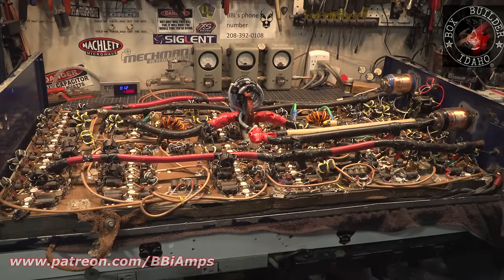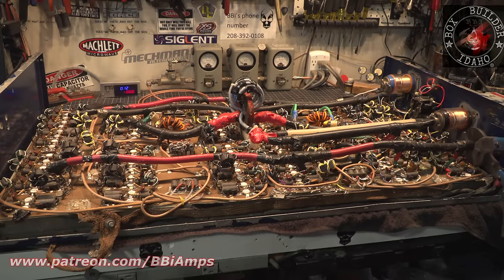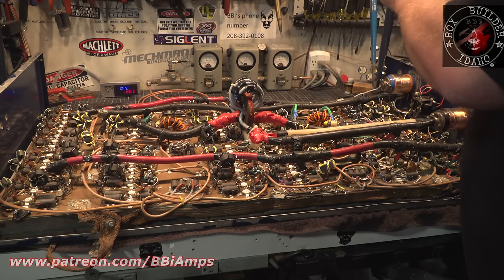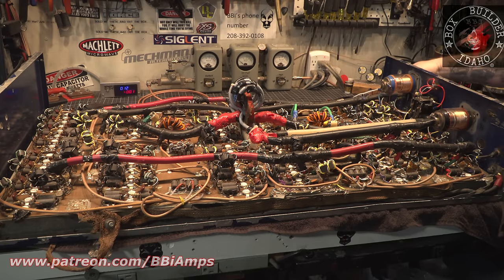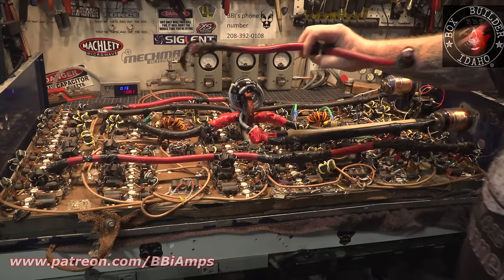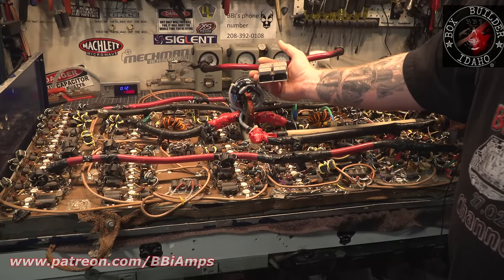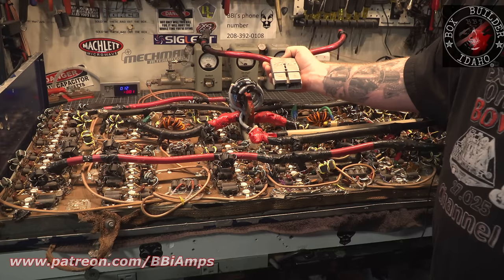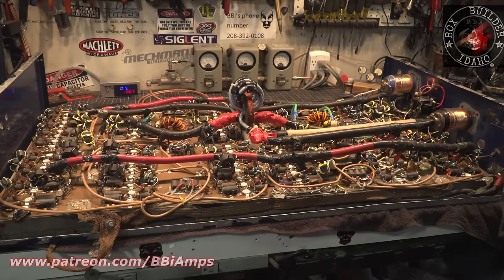So let me start here. I've been wanting to do this now for a week. Let's just start here. We'll come over here and we'll cut this aborted little piece of junk. They passed, this thing is gonna need 2,500 amps worth of shmoo, and they had it going through these two connectors on the positive side. There's 600 amps worth of capability here. So that means we left 1,900 amps worth of resistor heat. Just gonna throw that on the floor.